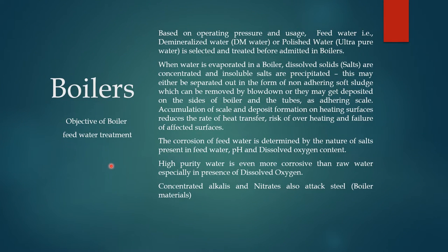Now we can see the objective of boiler feed water treatment. Based on the operating pressure and usage of the boiler, demineralized (DM) water, polished water, or ultra-pure water is selected and treated before being admitted to the boiler. For steam turbines, polished water is normally used, which has very low silica — less than 0.02 ppm — and very low conductivity. DM water is used in boilers for process service.